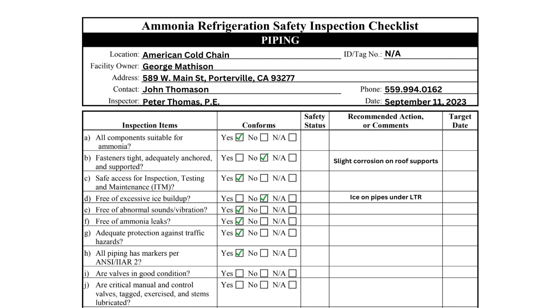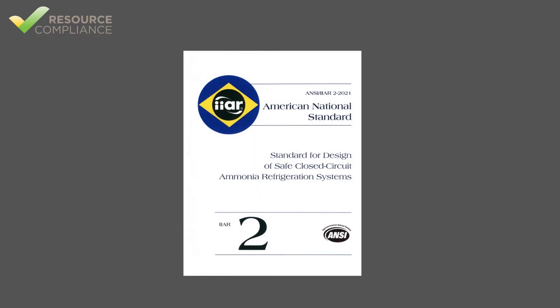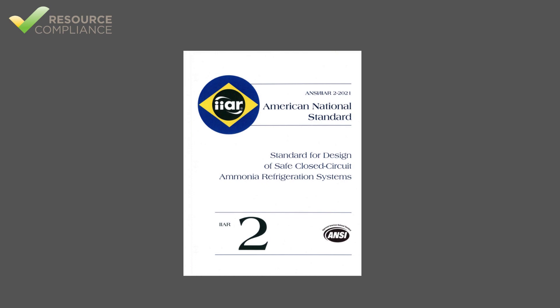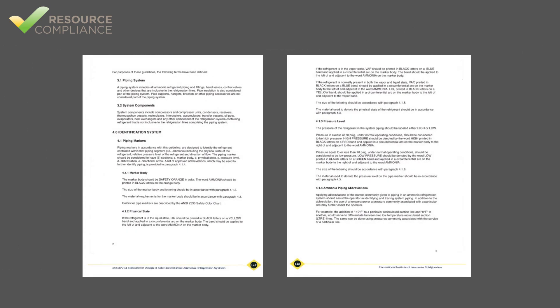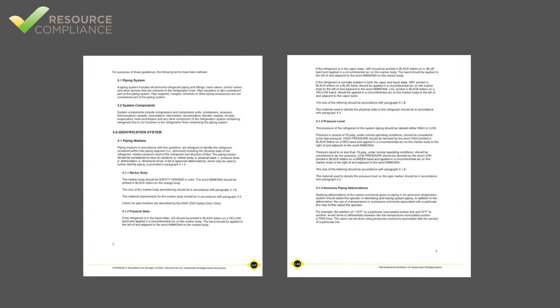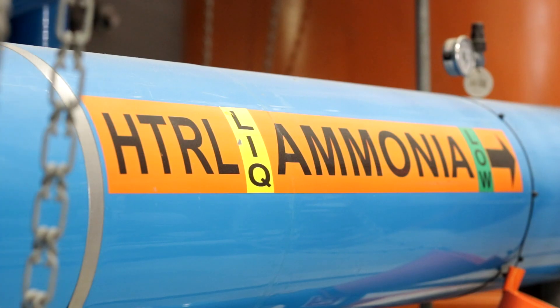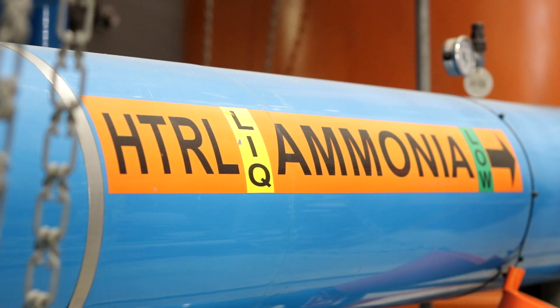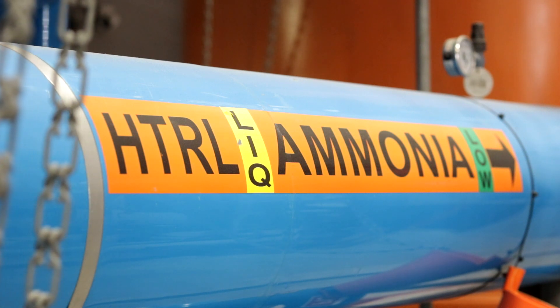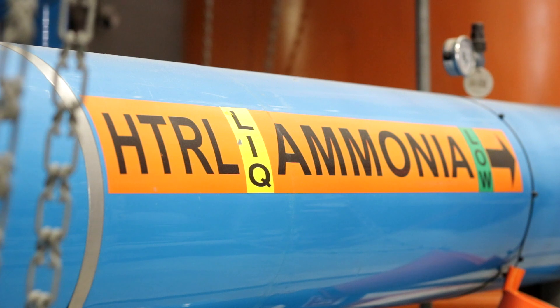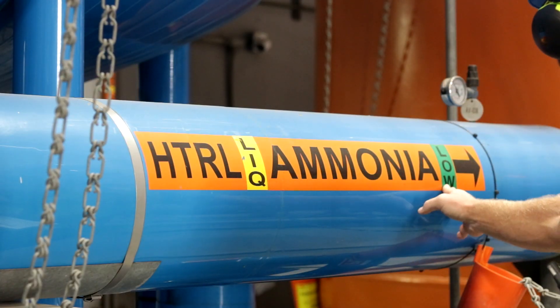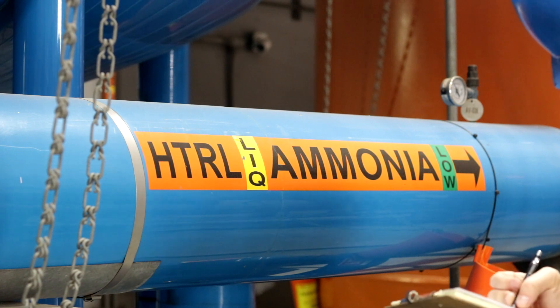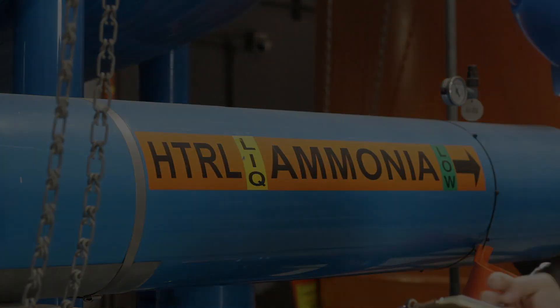Item H inquires if the pipes are marked as required by IIAR Standard 2. Standard 2 requires piping mains, headers, and branches to be labeled with the following: the word ammonia printed in black letters; the physical state abbreviation LIQ or VAP; the relative pressure, high or low; an arrow depicting the direction of flow in the pipe; and a service abbreviation indicating the purpose of the pipe.